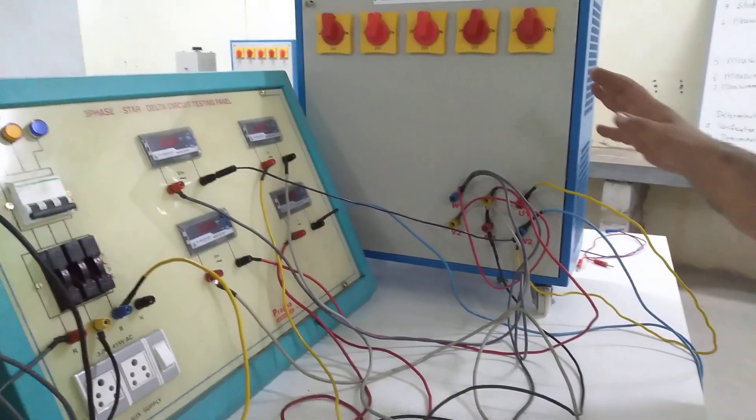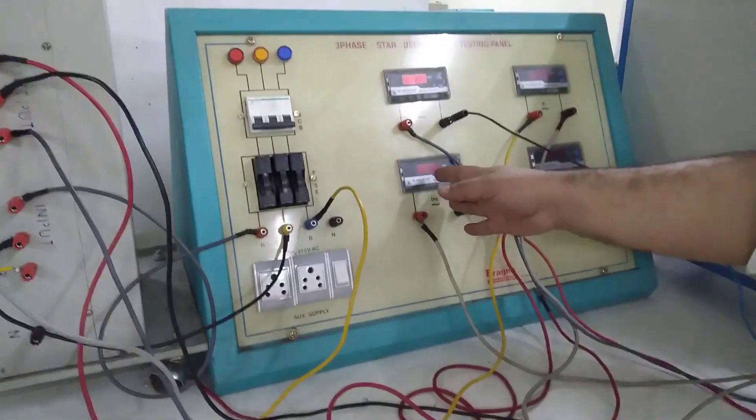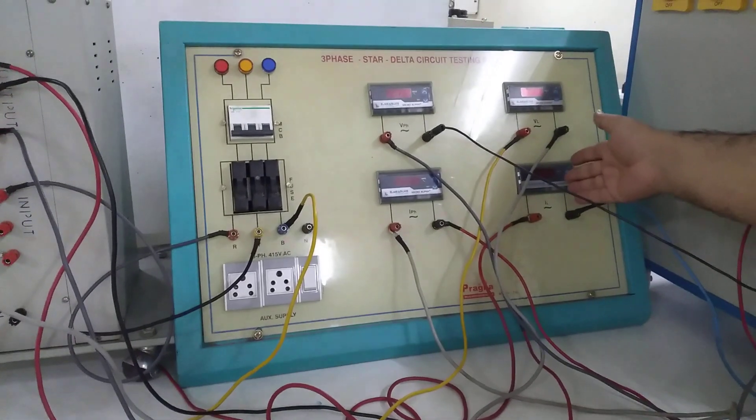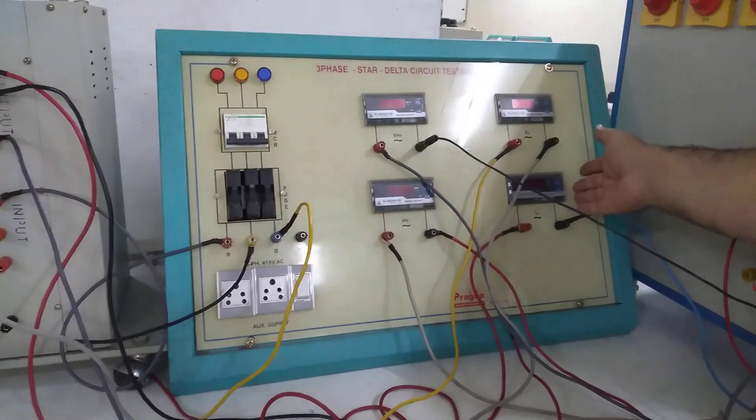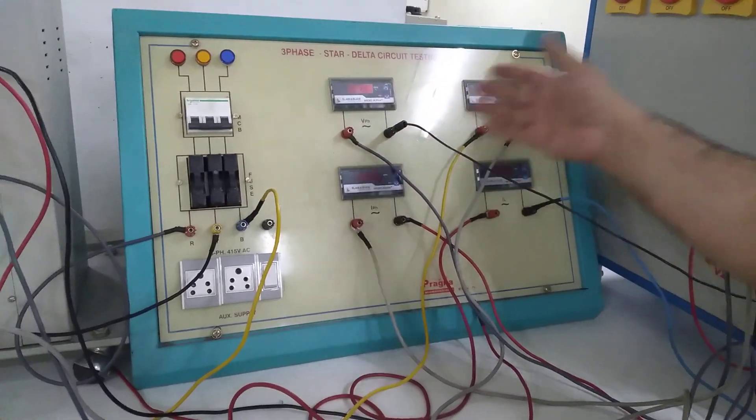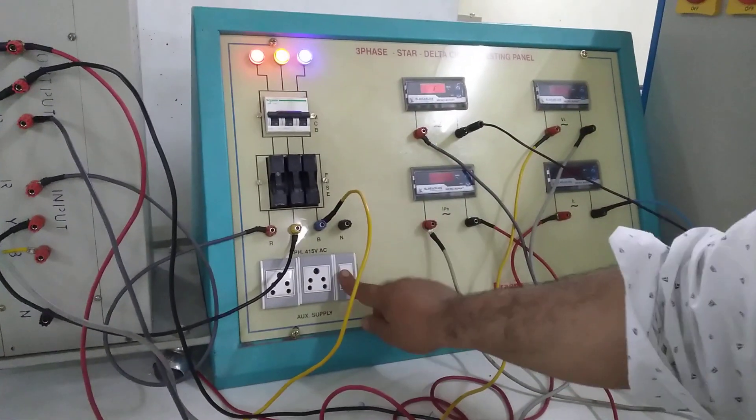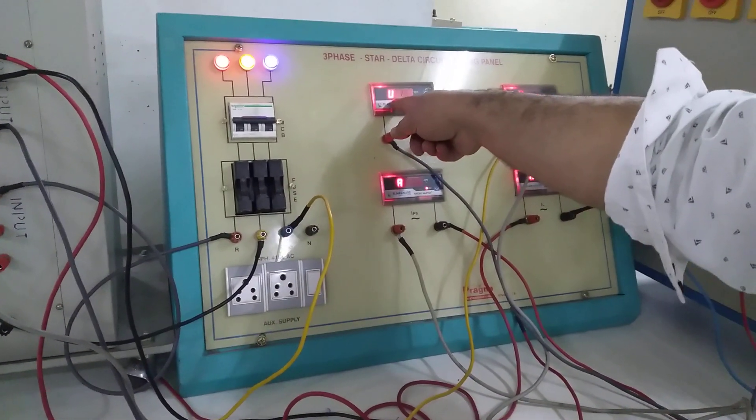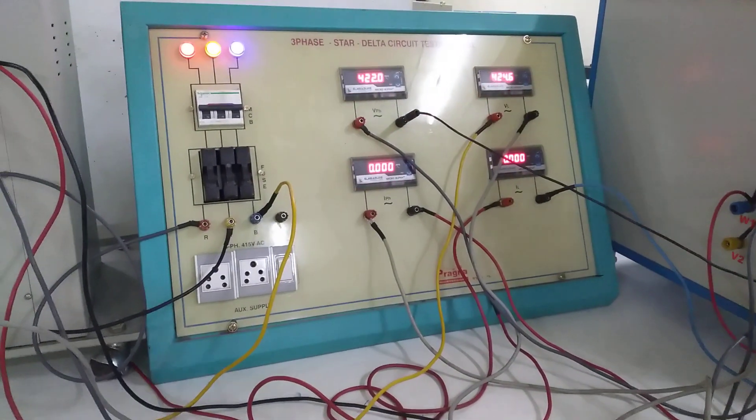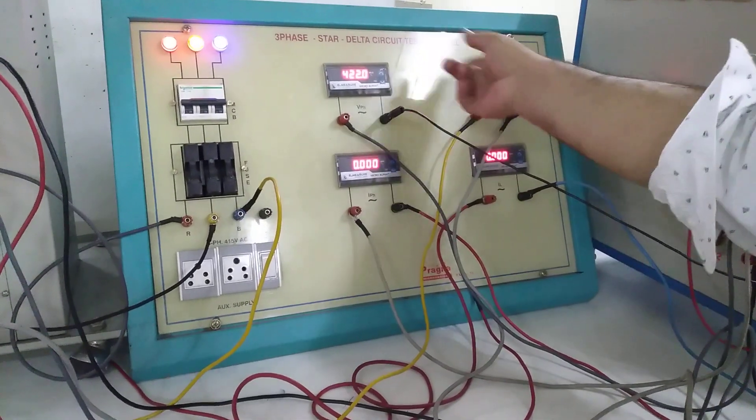In the delta connection, my V phase should be equal to my V line, and my I line should be equal to root 3 times I phase. Or I line should be root 3 times I phase, or I phase should be I line by root 3. So I am going to switch on the circuit. Just observe the voltages here. If you look at this, this is 422 and this is also same, almost same.